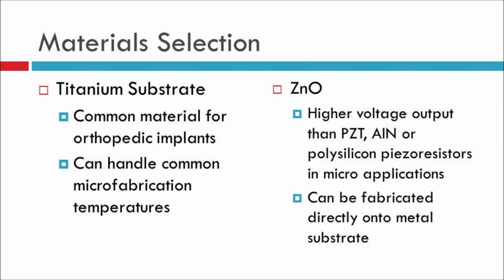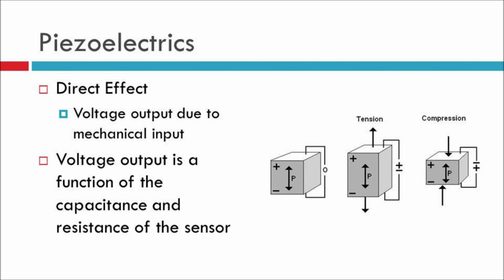For my materials, I have selected a titanium substrate, which is very common for orthopedic implants, and also can handle common microfabrication temperatures that are going to be used. For the piezoelectric, I'm using zinc oxide, which can actually be made to have a higher voltage output than PZT or aluminum nitride or polysilicon piezoresistors in micro applications. And another great benefit of zinc oxide is it can actually be fabricated directly onto the metal substrate.